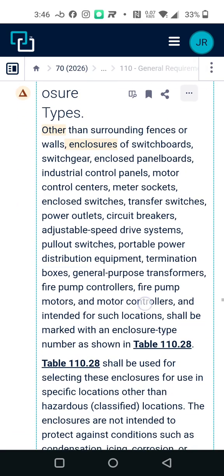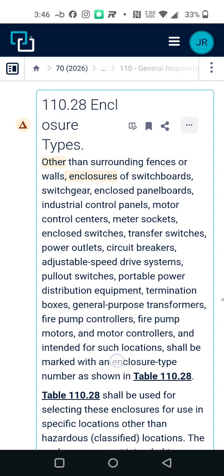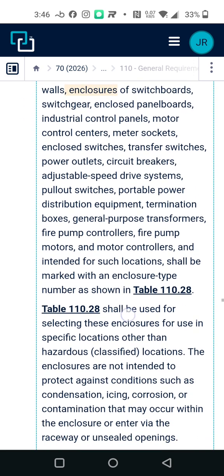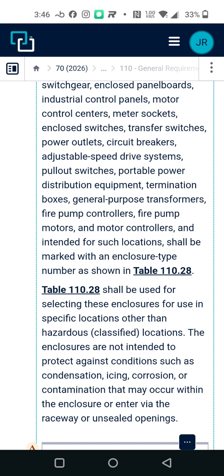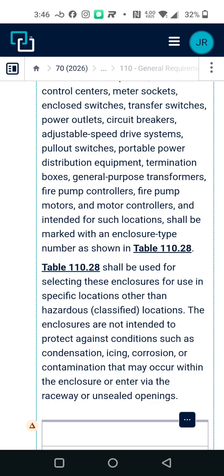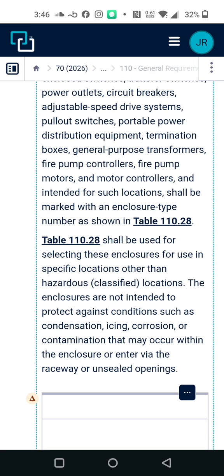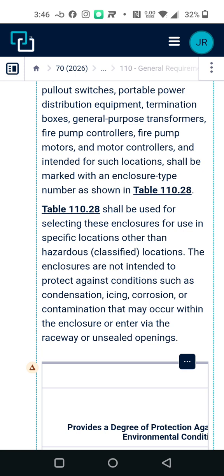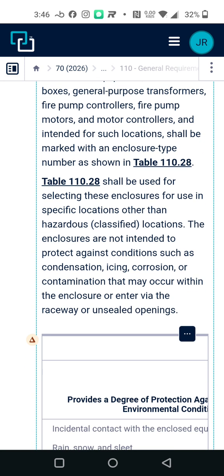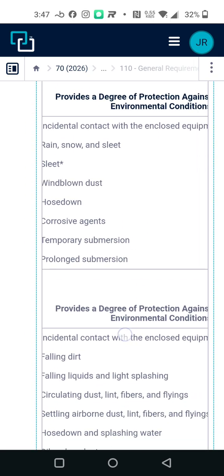Enclosure types. Other than surrounding fences or walls, enclosures for switchboards, switchgear, enclosed panelboards, industrial control panels, motor control centers, meter sockets, enclosed switches, transfer switches, power outlets, circuit breakers, adjustable speed drive systems, pullout switches, portable power distribution equipment, termination boxes, general purpose transformers, fire pump controllers, fire pump motors, and motor controllers intended for such locations should be marked with an enclosure type number as shown in Table 110.28. Table 110.28 should be used for selecting these enclosures for use in specific locations other than hazardous locations. The enclosures are not intended to protect against conditions such as condensation, icing, corrosion, or contamination that may occur within the enclosure or enter via the raceway or unsealed openings.